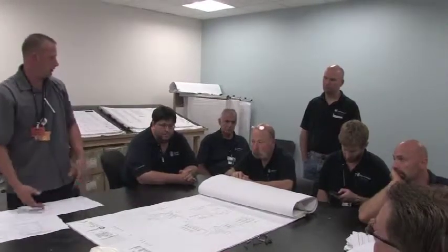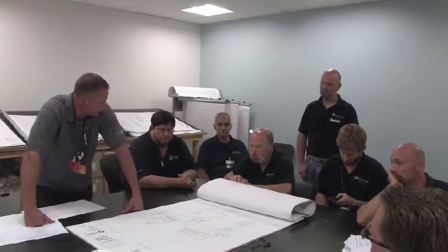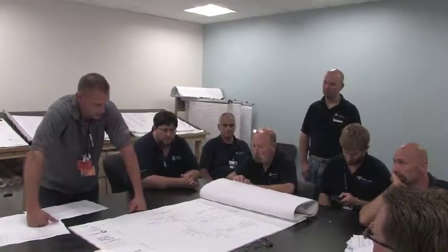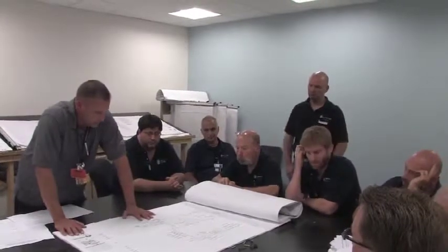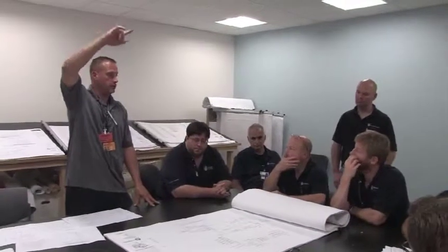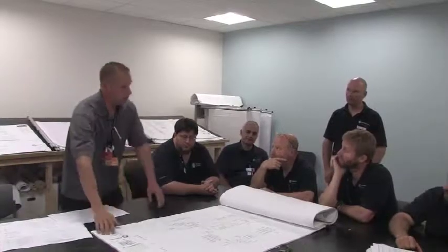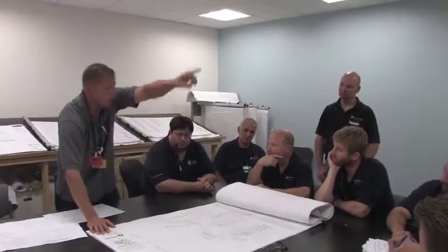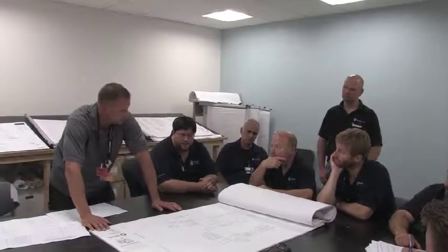Each floor has its own shut-off valves and balancing valves outside the shafts, and then every VAV box has a shut-off valve and a balancing valve. So it's pretty straightforward. The hot water starts in the shaft up behind the elevators. It runs from 10 down to 4. It cuts across 4. It picks up 1 VAV box in the elevator lobby on 4. And then it goes down this back shaft over here, right behind this wall. So it goes from 4 down to the sub-basement.